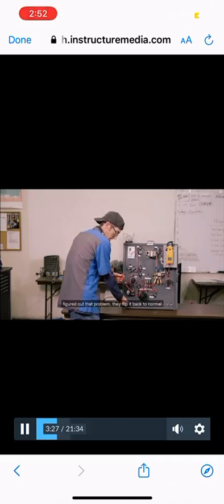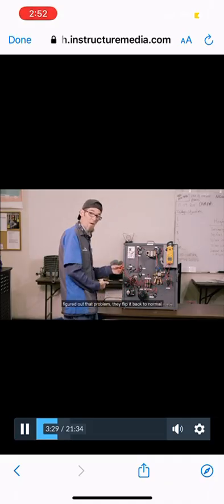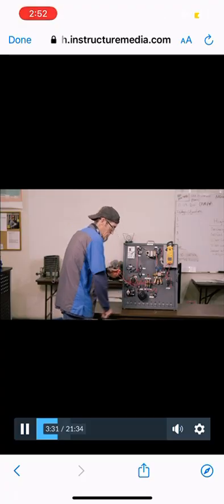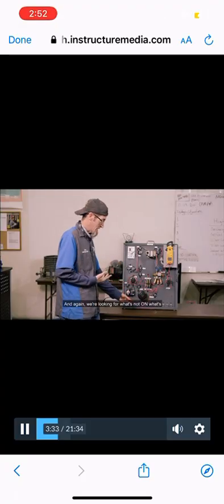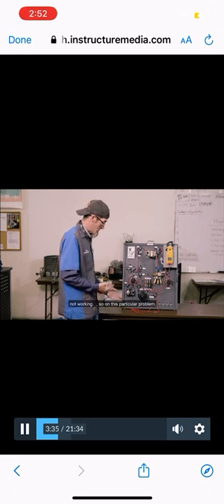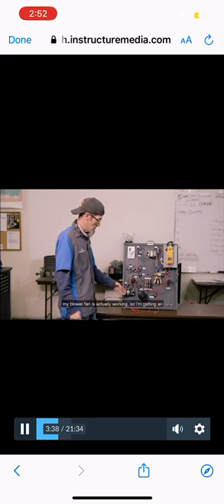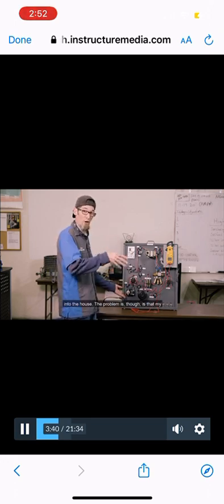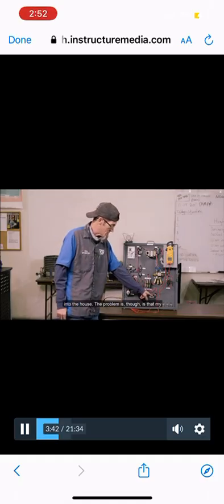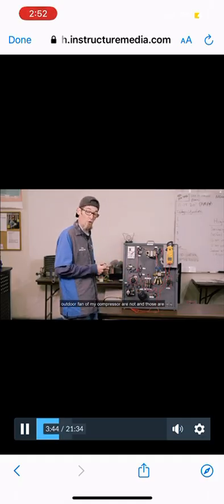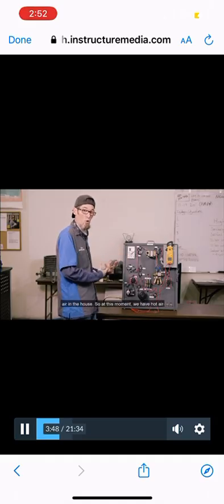Once the students are done and they've figured out that problem, they flip it back to normal. They move on to step 2. And again, we're looking for what's not on, what's not working. On this particular problem, my blower fan is actually working, so I'm getting air into the house. The problem is that my outdoor fan and my compressor are not. Those are what's going to move that refrigerant around and actually make the refrigerant cold so I can get cold air in the house.